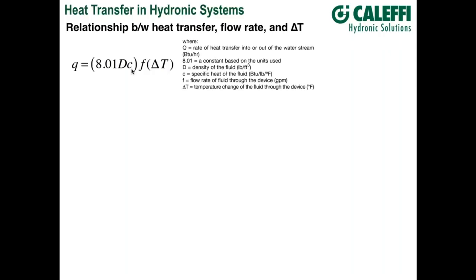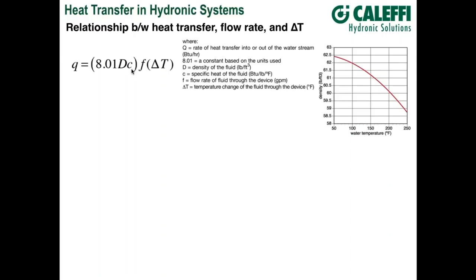The graph shows the variation in density for water over a temperature range of 50 to 250°F — it's significant enough that for precise calculations like BTU metering, you need to factor in this change in density. The simpler formula most people use in hydronics is: rate = 500 × flow (GPM) × delta T. The number 500 is what you get assuming 60°F water — taking the density of water at 60°F (roughly 62.4) and a specific heat of 1.0, you get approximately 499.6, rounded to 500.